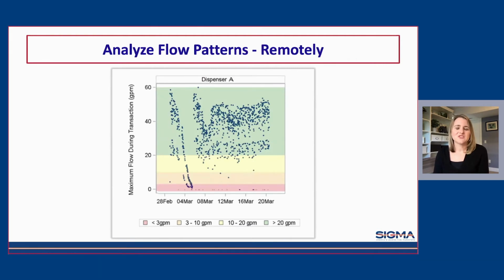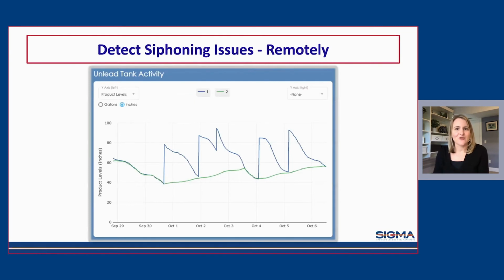Also helpful in situations like these is the ability to analyze flow patterns remotely and put a flow issue in context. You can look visually and see: did this problem develop very rapidly, perhaps in response to an event like a delivery? Did it affect all dispensers at once or just a few? Or is this a problem that's been building very slowly over time? If you see a pattern like the one shown here, showing very erratic flow patterns, not just across this dispenser but all dispensers pulling from the same tank, that clued us into a rag that had been caught in the STP. These patterns are just very exciting to get to know and analyze.